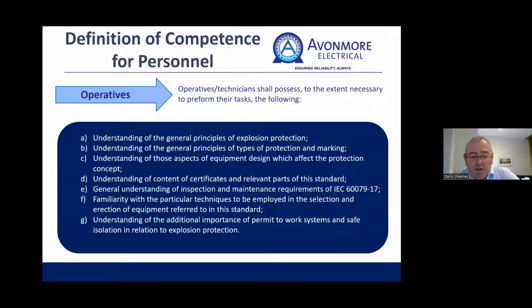That's very important there when it relates to certificates. On every EX piece of equipment, you have a certificate number. And typically, if you have the letter X after the number, it means there are special conditions on the use or the safe use of that particular piece of equipment.